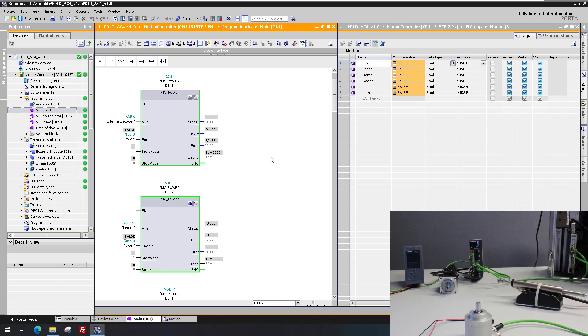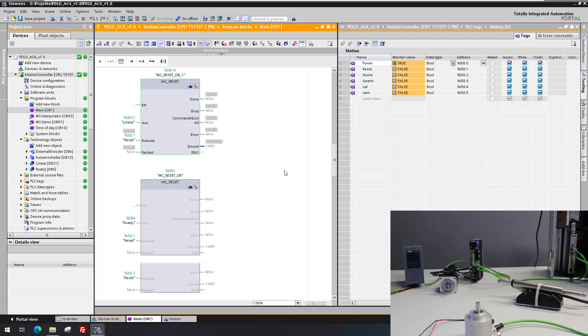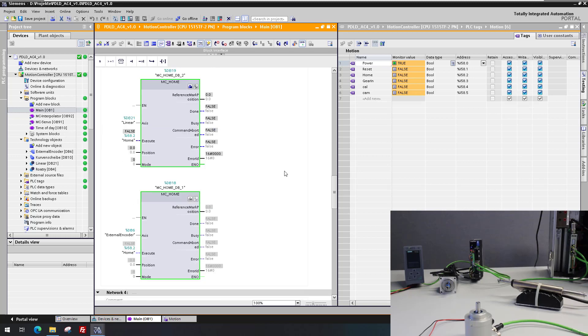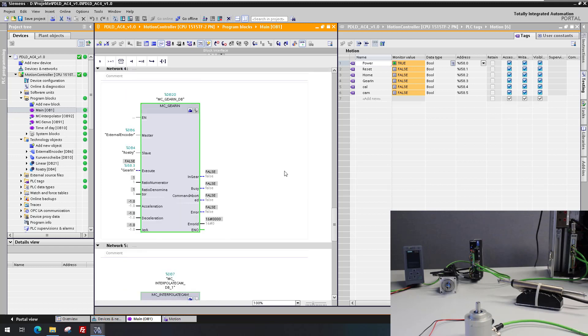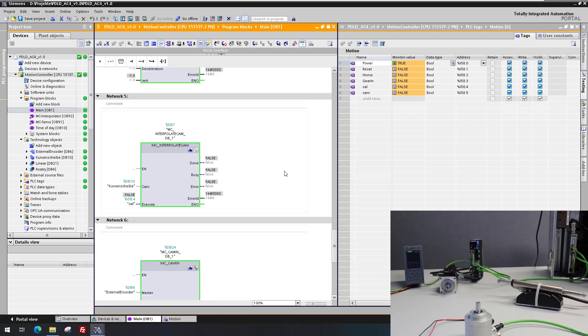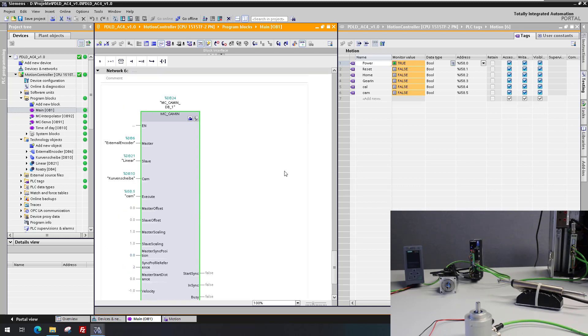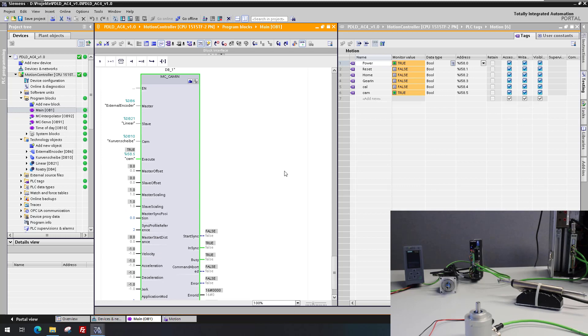The inputs for the used motion control blocks are visible in the online view of the PLC. First, all objects are enabled. The homing for the linear axis and the external encoder is executed. Next, the gearing between the external encoder and the rotary axis is executed. The cam is calculated, and the synchronization between the cam and the linear axis is enabled.